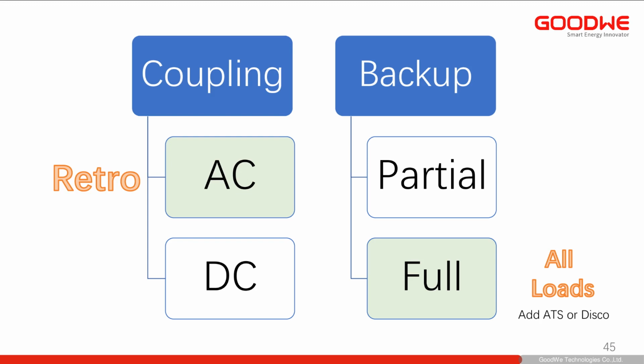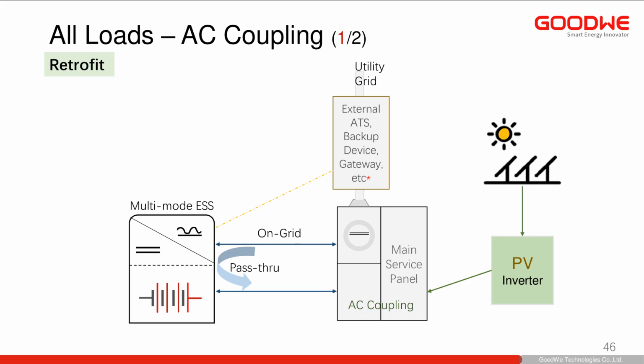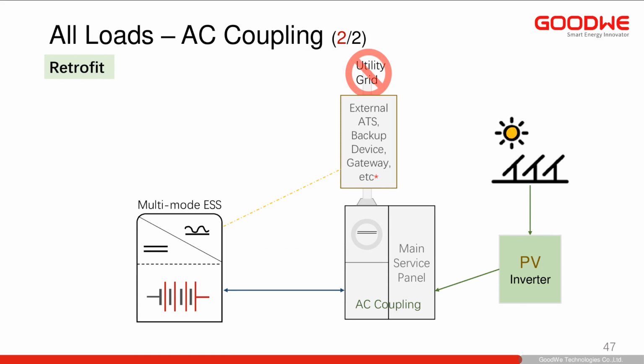We can also do retrofits, and full loads in a retrofit scenario. Again, we have the PV inverter connected to a load panel, but this time it's a main service panel, doing its AC coupling there rather than through an essential loads panel. So we don't have to move the PV breaker out of the main service panel to another backup panel. It operates basically the same way.